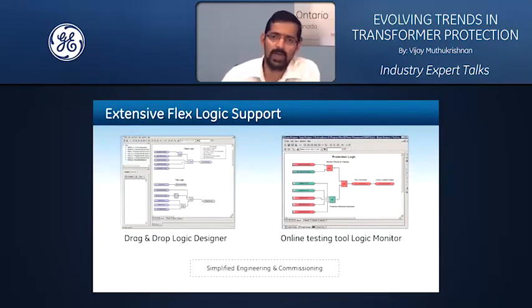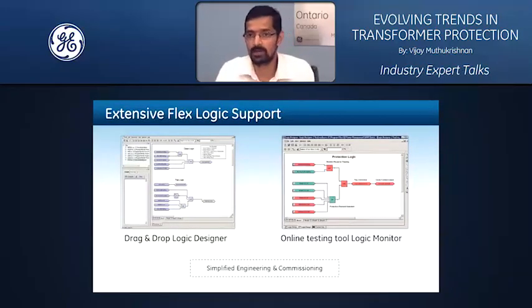Then the next one is, okay, you have been able to do without any logic a good deal of your functionalities. But there are cases where you want to build some custom interlocks, some custom control logics, such as cooling control logic, or you want to do upstream interlock with the device that you have. You want to do some FlexLogic functionalities. We provide an ability to do graphical programming of the logic in a graphical editor, and even when you have built it, you want to test it, you have a graphical way of following through in real time the state of various intermediary states within your FlexLogic engine and test the FlexLogic you have built. It really expedites your ability to build logic and test your logic. That is the value behind these functionalities.